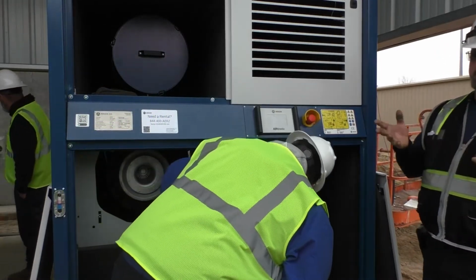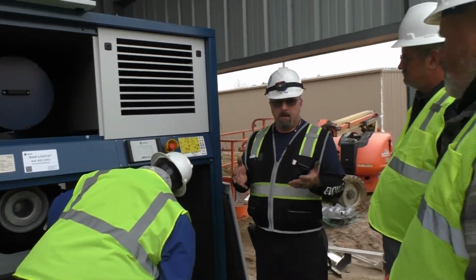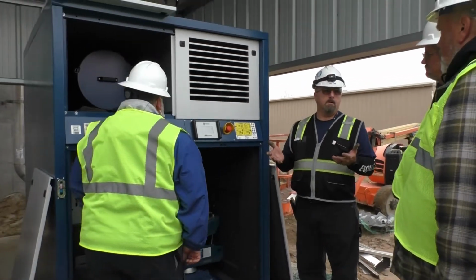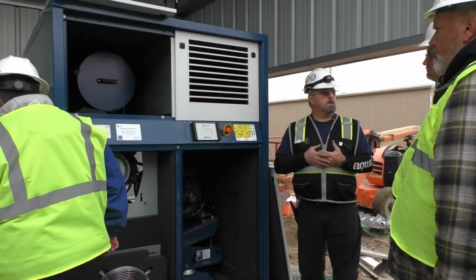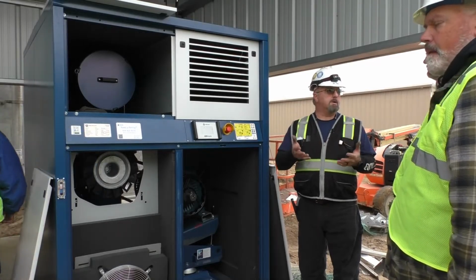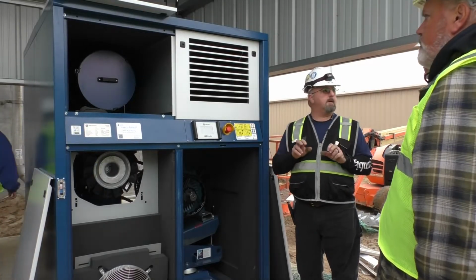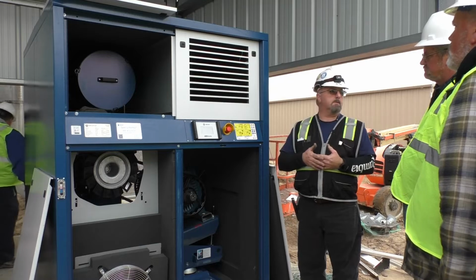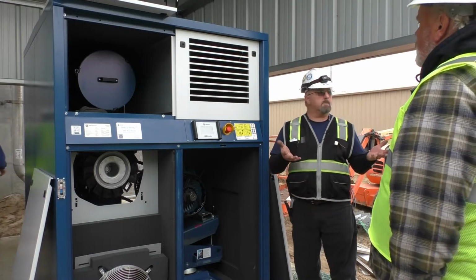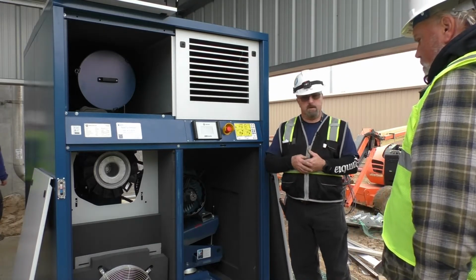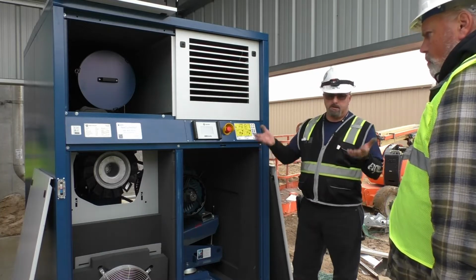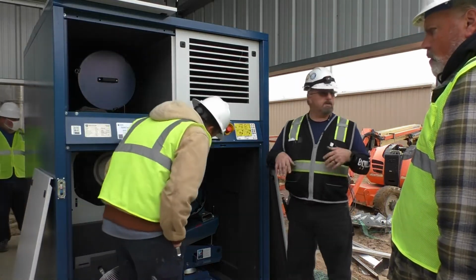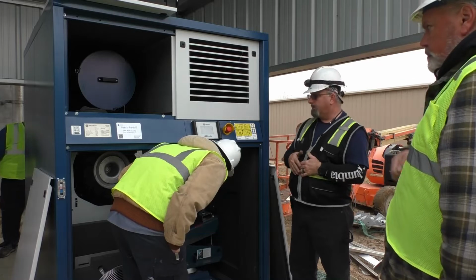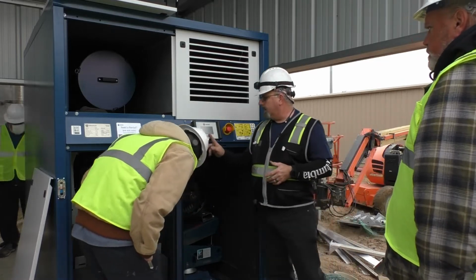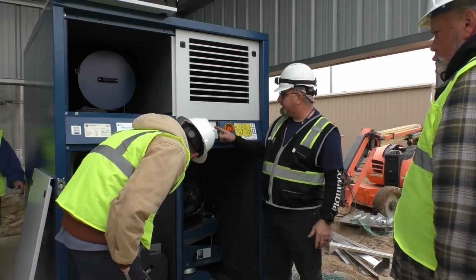Because when I first start them up and do the run testing, I'm going to be running them at max speed, max pressure. So that'll tell me what should be a typical average for this time of year. Now I can't tell you the hot weather one just because it's not hot. And as your ambient temperature increases and decreases, you will see that temperature fluctuate a little bit. So you only have one temperature just for the discharge.